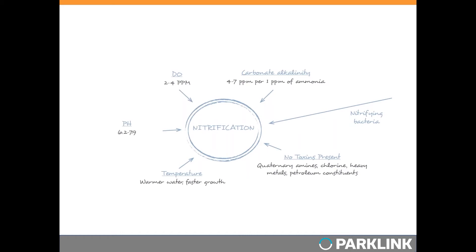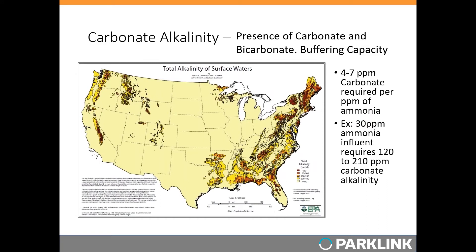Another important factor is carbonate alkalinity. In contrast to heterotrophic floc formers, autotrophic nitrifiers use inorganic carbon as their carbon substrate — for cellular components and to make their own organic carbon for energy. Carbonate alkalinity is not the same as hardness — hardness refers to divalent cations like magnesium, calcium, iron, or manganese. Both are reported in terms of parts per million of calcium carbonate, which causes confusion. Alkalinity measures the buffering capacity of water — the amount of hydroxides and carbonates that can neutralize acids — and this is not the same as pH.